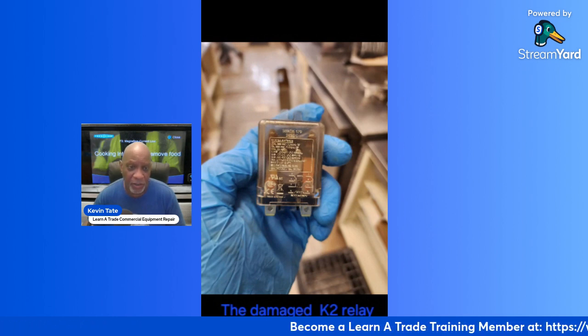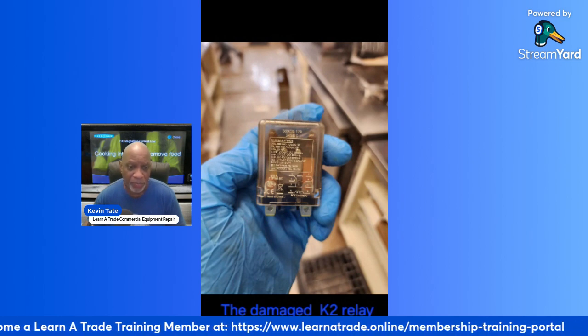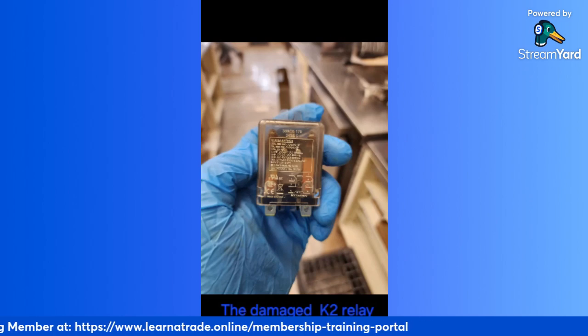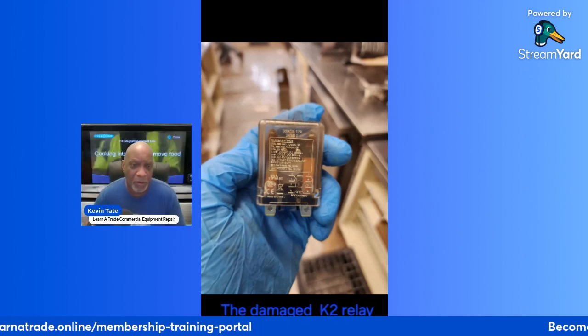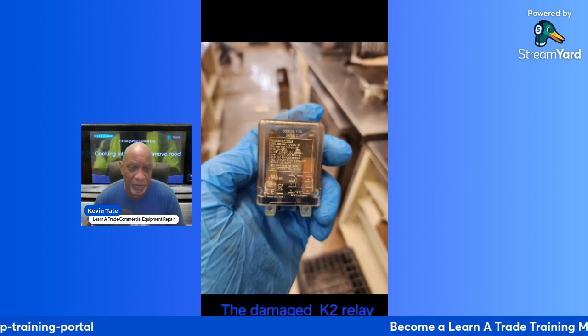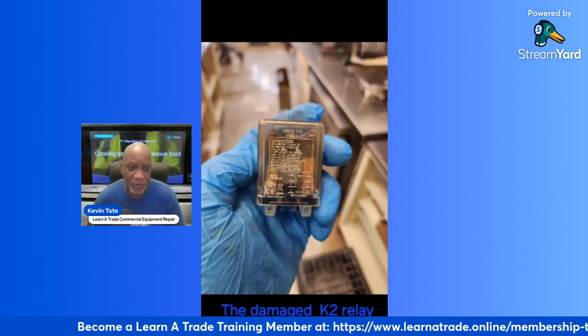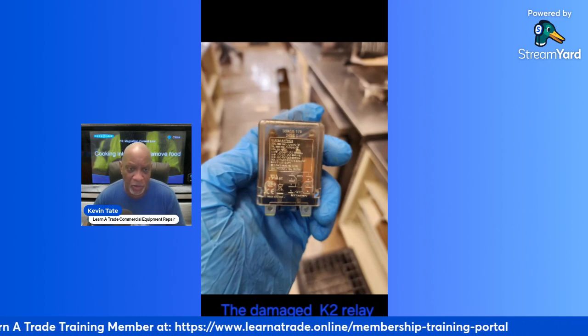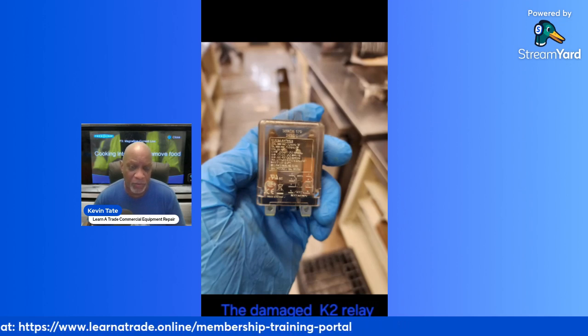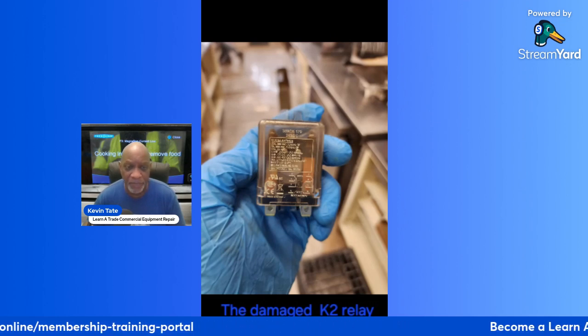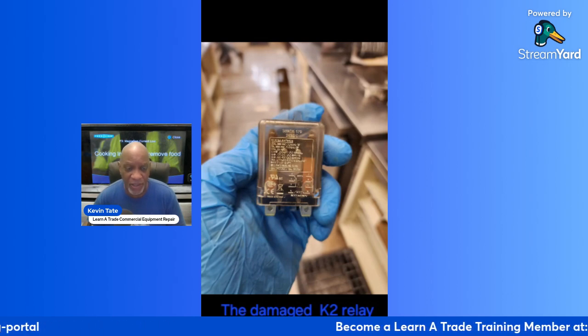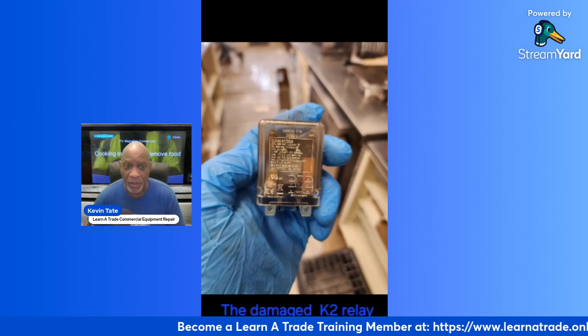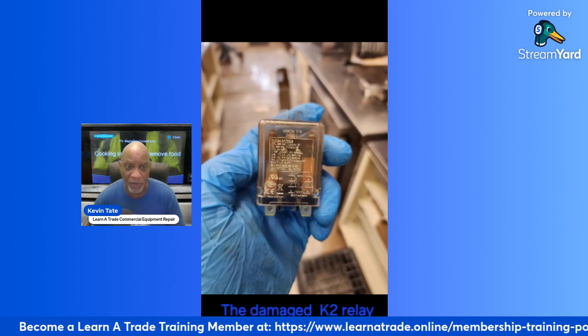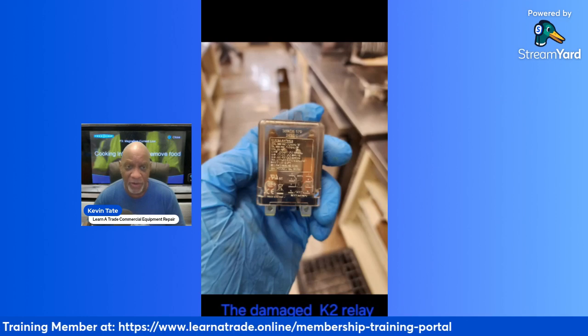And this right here is the K2 relay that I was talking about. I'm not sure if you could see it that well, but on the left side, that copper contact there, a little contact. You see the contact on the right? It looks clear. You can tell that it's clear. The one on the left, though, you can see the discoloration in that copper contact. So that's telling you that there's a short on that side of the relay. So you will want to replace that relay.